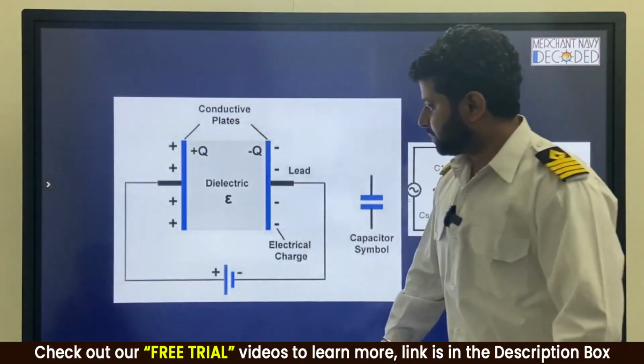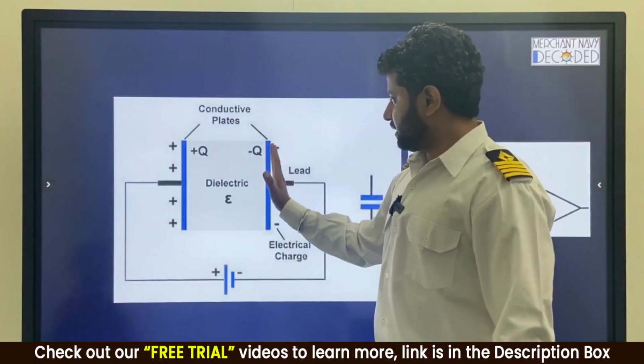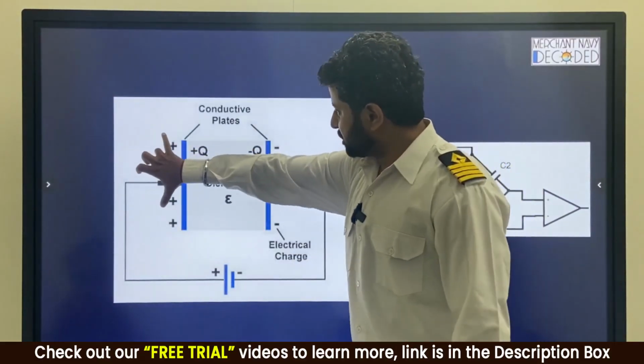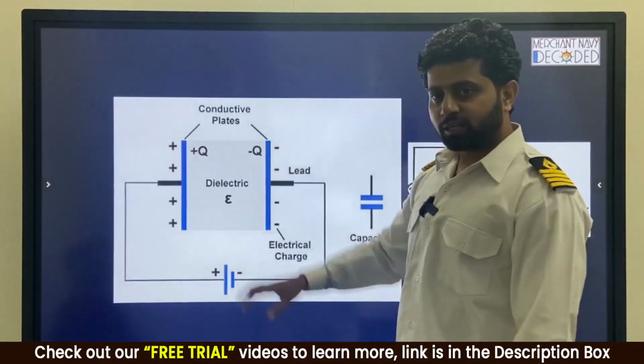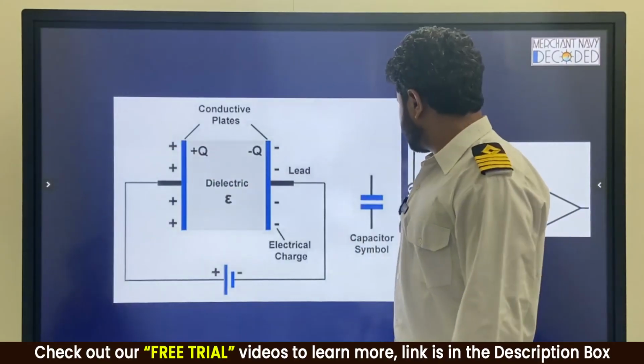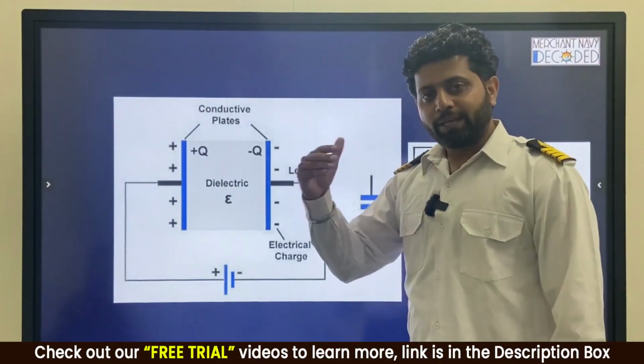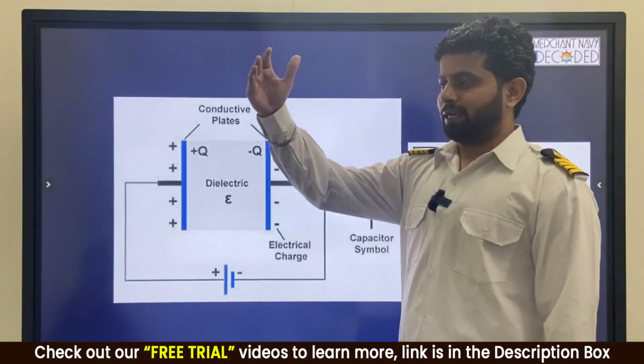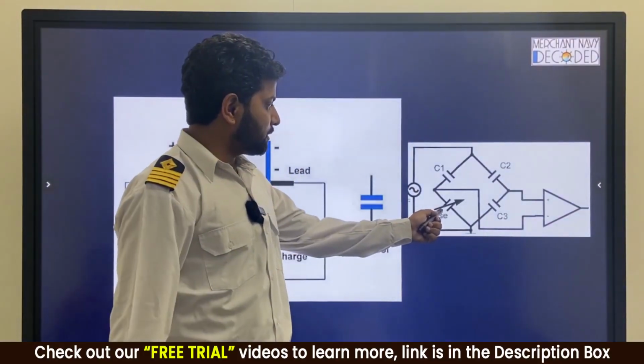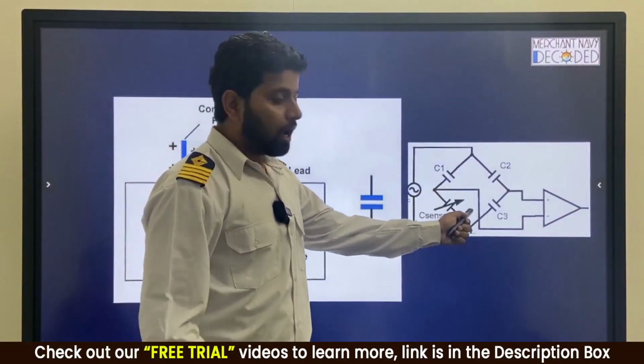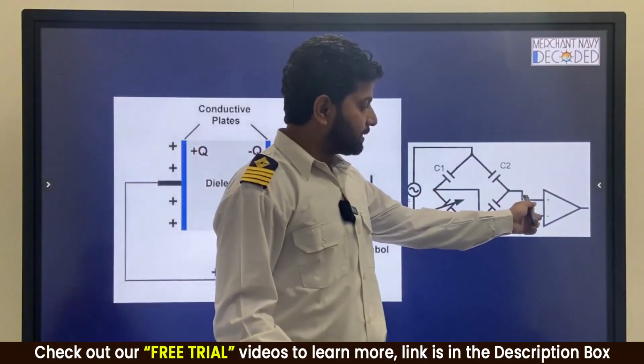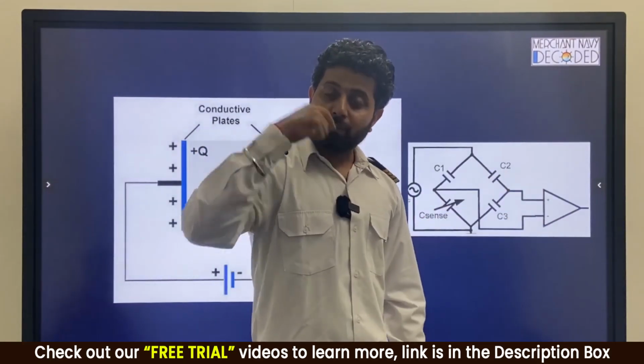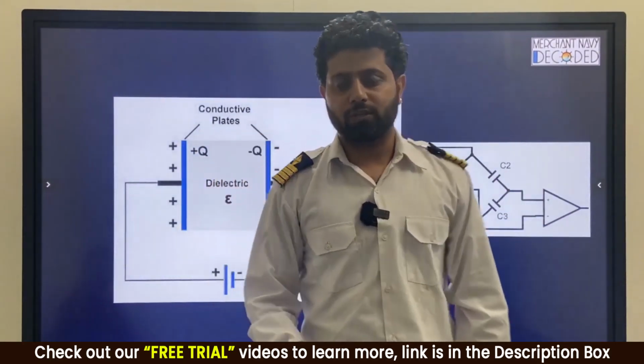Copied, guys? Another is the capacitive type. Simple. Say this is a fixed plate and this is a moving plate. If the pressure is acting from here, the distance is going to decrease. If the distance decreases, C is equal to epsilon naught A K by D. If D decreases, your capacitance increases. Your capacitance changes over here. This becomes an unbalanced Wheatstone bridge. The current signal comes, we amplify, and from that current signal we get an idea, acha bhai, what is happening.